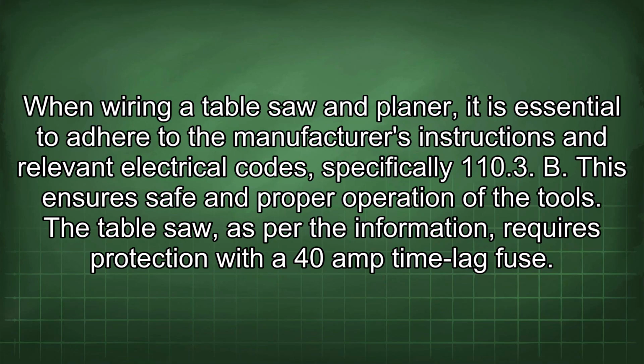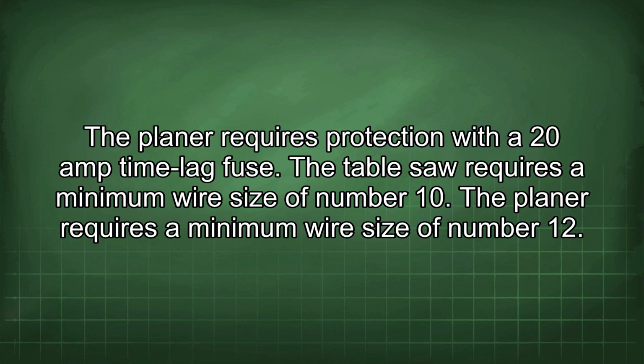When wiring a table saw and planer, it is essential to adhere to the manufacturer's instructions and relevant electrical codes, specifically 110.3. This ensures safe and proper operation of the tools. The table saw, as per the information, requires protection with a 40 amp time lag fuse. The planer requires protection with a 20 amp time lag fuse.